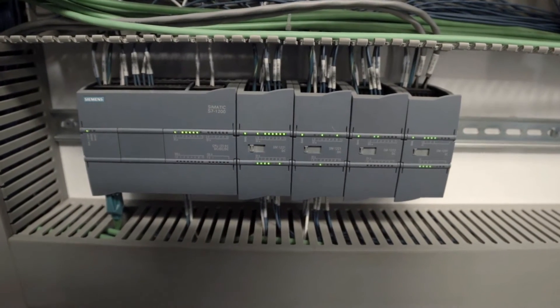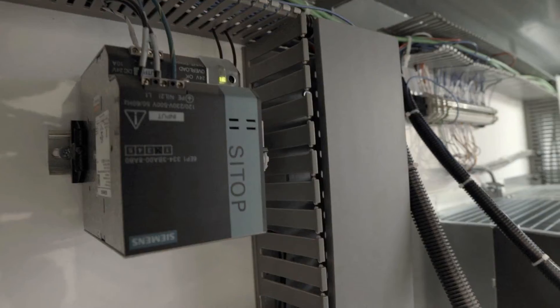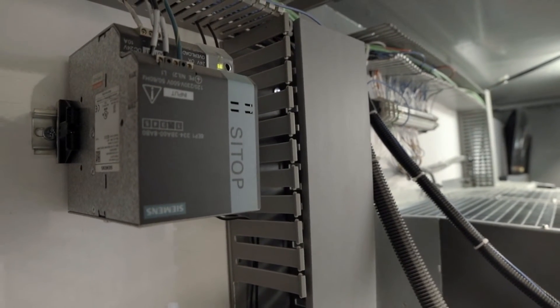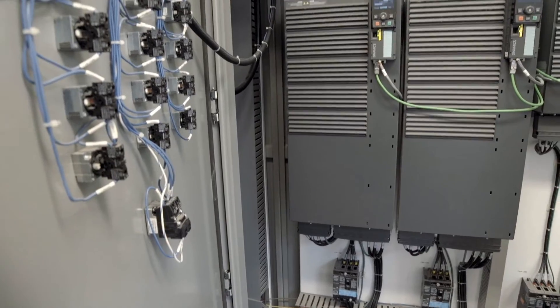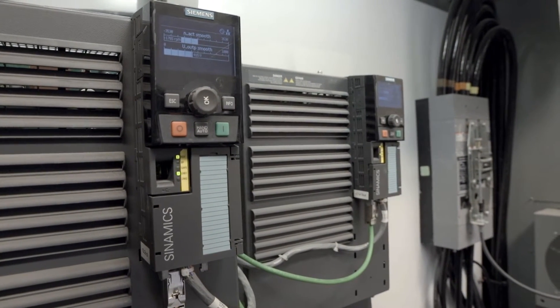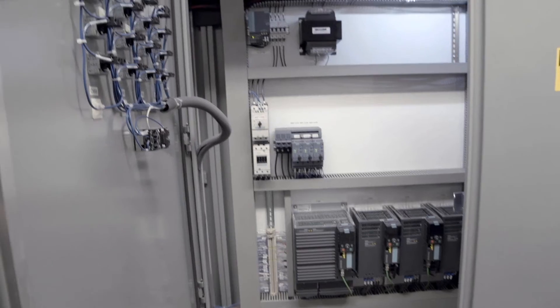All motor circuits are communicated and controlled by the PLCs over Profinet. Instead of having a traditional motor starter with a dozen wires, we have one communication cable to that motor starter and protector. It allows troubleshooting to be done much quicker. The other nice thing about using TIA Portal — we had a large number of options for integrating separate controllers, whether that was communications, remote I/O, or adding a very small PLC and then adding that to a Profinet network. We had all those options at our disposal.